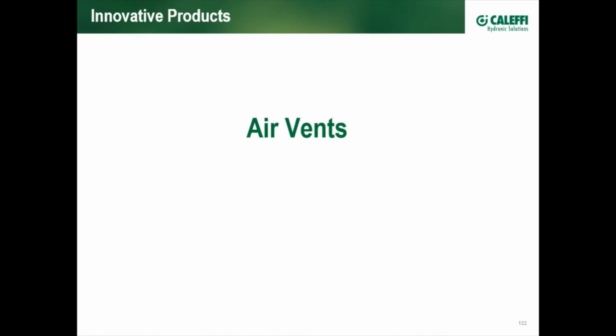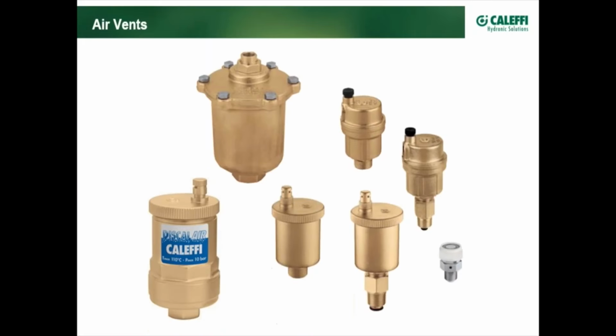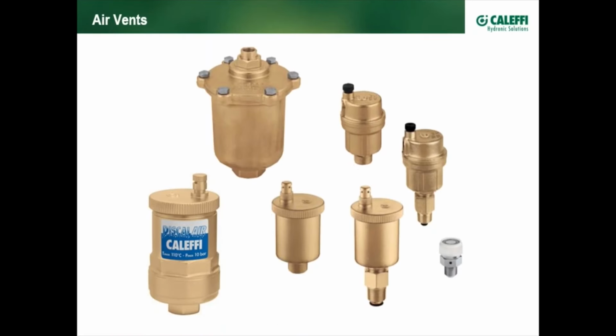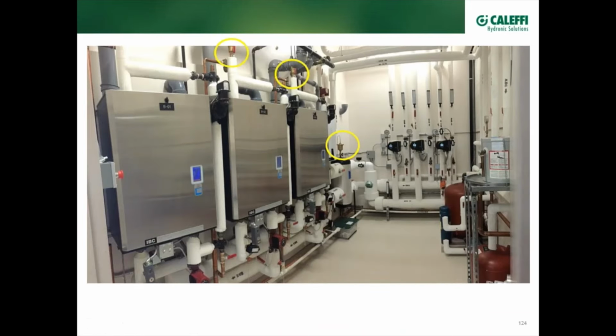A couple more products, then we'll wrap it up. Air vents, they're worth noting. Caleffi is, like I mentioned, maybe the biggest in the world in air vents production. High capacity, lesser capacity, they're used. Many contractors will use them everywhere. At the top of boilers, as mentioned, we have it standard at top of our hydraulic separator. And on these secondary pumps going up, if this is a multi-story building, at the top of those risers, perhaps there is also automatic air vents.